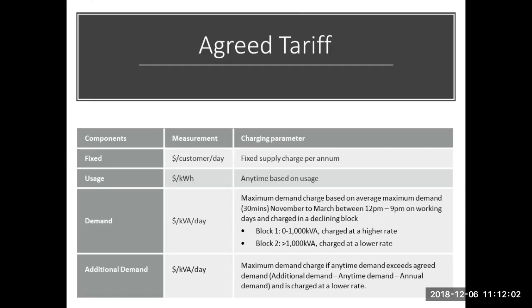So if you do start to peak in your demand and you can measure it and you can see it, and let's say you've got an internal alarm at your winery that says we have peaked at, let's be realistic and say 400 kVA, because then if it's 400, it could peak at 450, 600, 500, etc. You're going to be paying more money for the next 12 months. But if you then switch off a few pieces of equipment, you can drag that average demand back down again, back to within what you've already agreed for, so you don't have to pay additional charges.